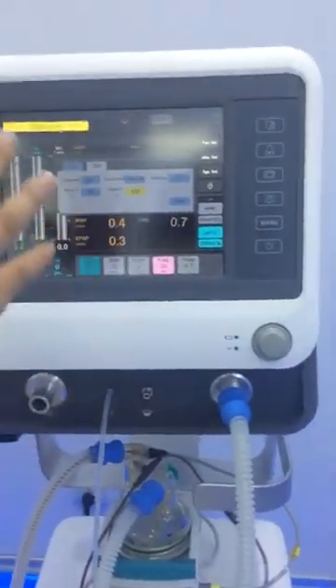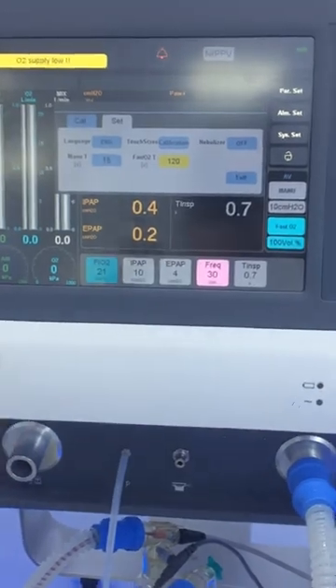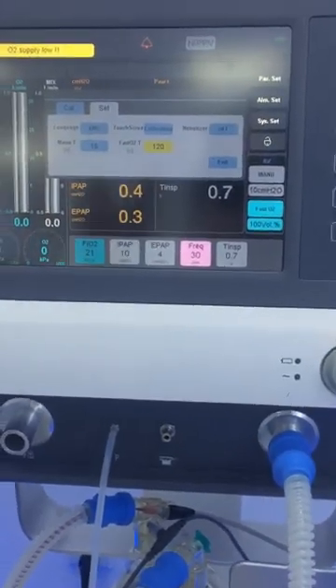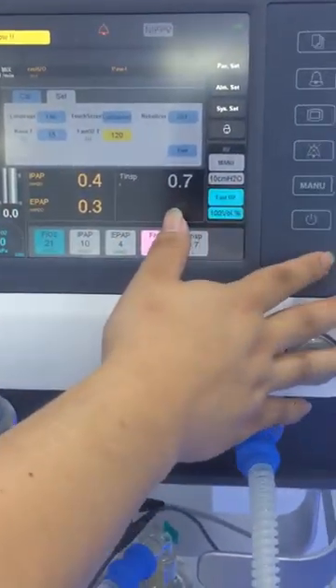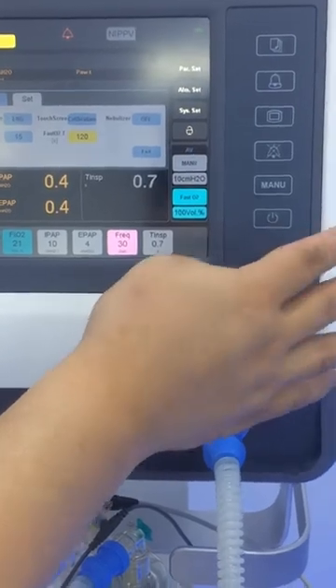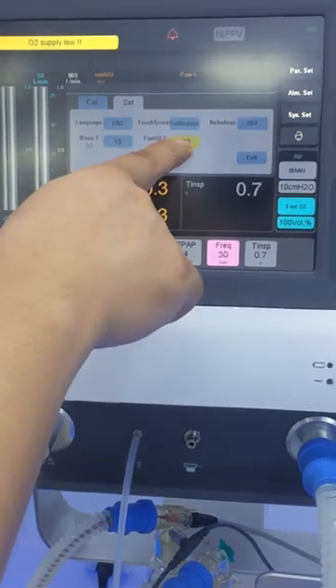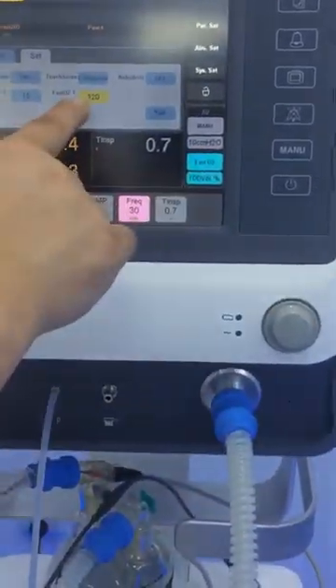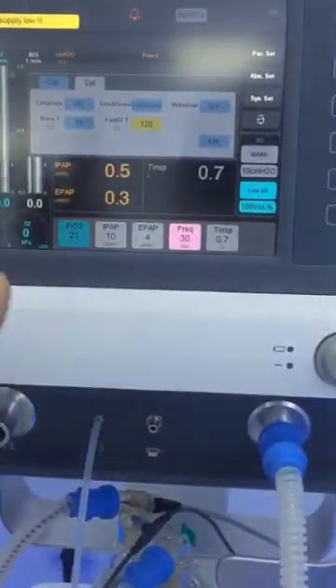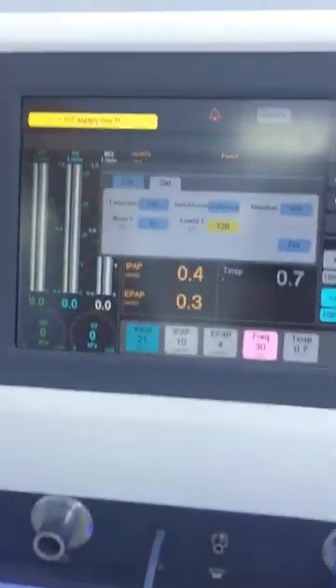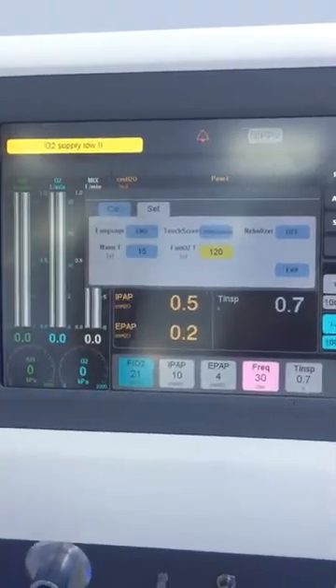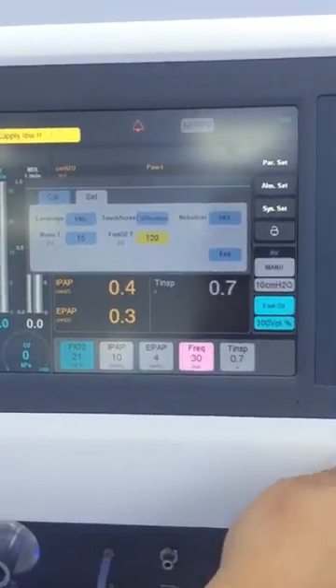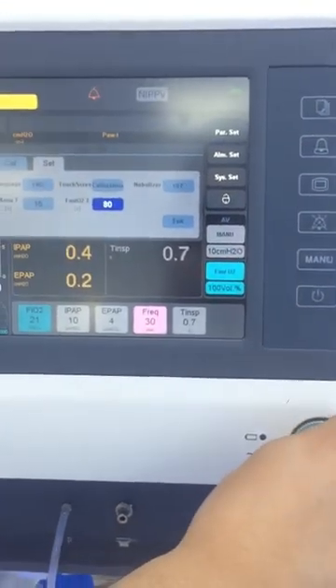The last one will be the rapid oxygen supply, but this one has an integrated function. We know usually on the machine we need to press a button for the oxygen rapid supply one time by one time, but for this one it's automatic. That means you can see here we can set. If we set 120 seconds, that means once we start the oxygen rapid supply, it will run for 2 minutes. And if we set it to 80, then it will be 80 seconds, very automatically.